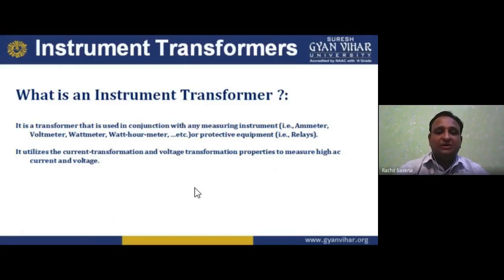It is a transformer that is used in conjunction with any measuring instrument, that is ammeter, voltmeter, wattmeter, watt hour meter, etc., or protecting equipment, that is relay. It utilizes the current transformation and voltage transformation properties, or we can say the properties of the transformer, that is the transformation ratio, to measure high AC current and voltage. So we can say instrument transformer we are using to measure high voltage and current, because ammeter and voltmeter have certain limitations. For example, a voltmeter we can use at maximum for 220 volt measurement.